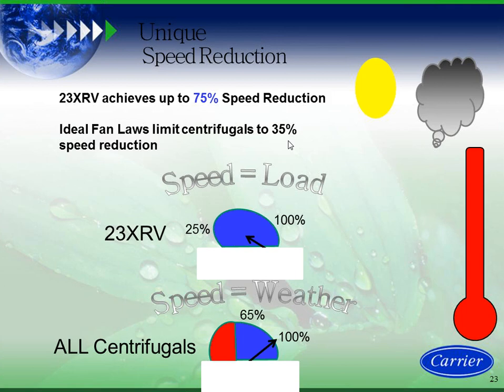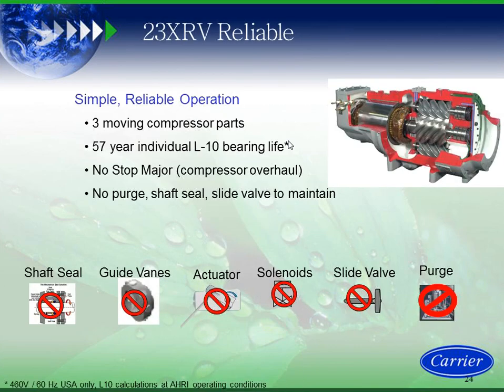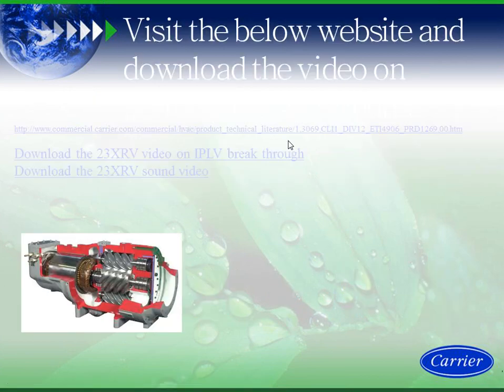And we sell centrifugals too. Our 19XRV is a very efficient machine. I'm just showing you the differences between our tri-rotor 23XRV and all centrifugals. Again, simple, reliable, three moving parts, 57-year individual L10 bearing life, no stop majors. I have no purge, no shaft seal, no valve, no slide valve maintenance.